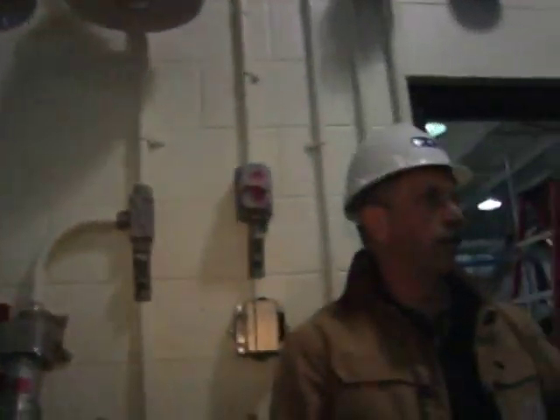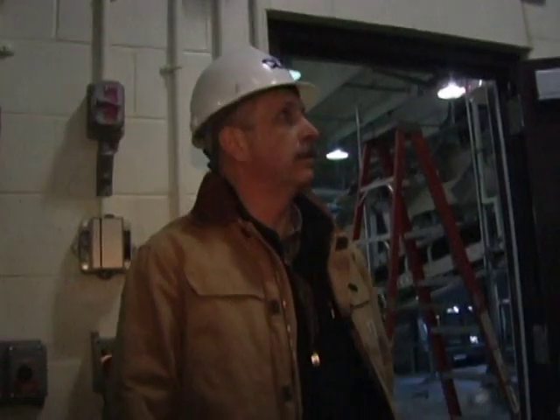Once the generator comes online through the loss of utility power, then your normal overhead lighting will come back on within time. These take a little bit of time to cool down and then re-spark themselves. In each of the rooms, there are at least one, I believe there's 3 in this room, in the screenings room itself, that have a quartz light associated with them, so you'll get some light coming on immediately, and then after the lights go through a cool down process, they'll spark back up and come back online.